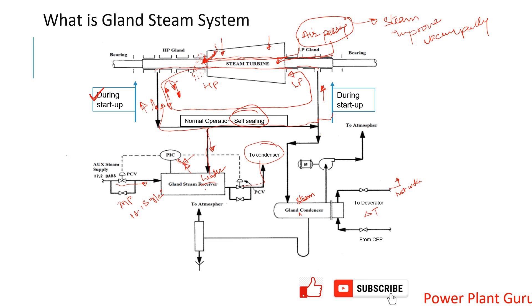At some plants, in this condenser there will be some non-condensable gases as well present in this system. We have to put a kind of ejector or vacuum pump there that keeps maintaining vacuum here. But in some cases, if there is auxiliary power consumption and if the motor is replaced by steam ejector, that will use steam. So you have low auxiliary power consumption. This is the entire story of gland steam.